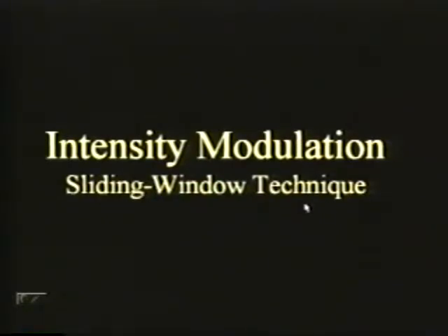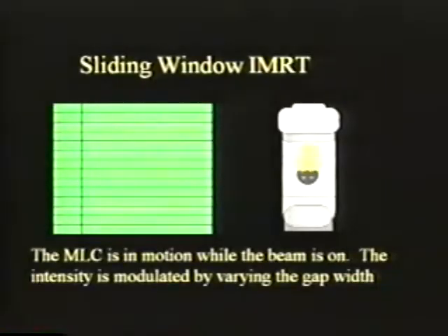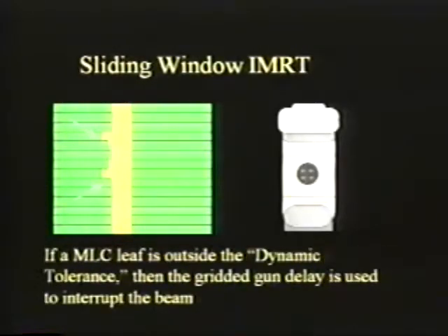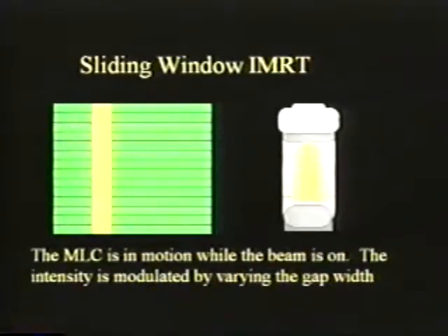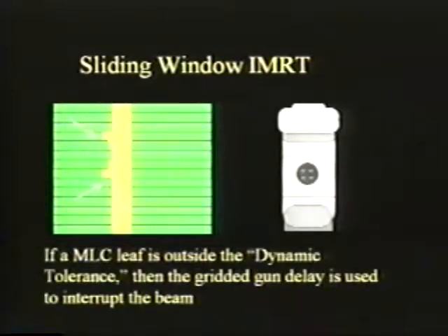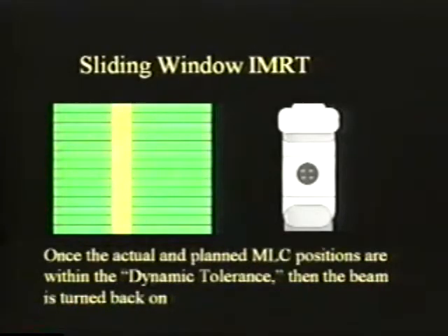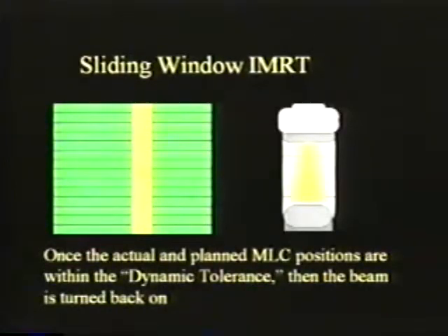Another type of intensity modulation is the sliding window technique. In this technique, the MLC is in motion while the beam is on, and the intensity is varied by changing the gap width between the two leaf banks. The only time that the beam turns off is if the motors driving the multi-leaf collimator leaves are not able to keep up with the planned position, then the beam will hold off until these leaves catch up to the correct position and then turn back on. But that's all automatic under computer control.